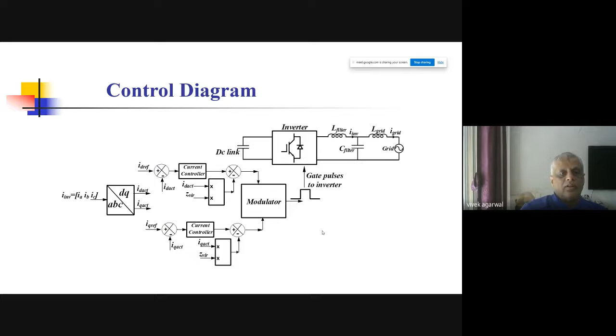Here is another example showing how you can use the sensed inverter output current to do protection. We've inserted an impedance such that at the time of starting the system, the large current coming out of the inverter and going into the system should be prevented. But we don't want this impedance to be there throughout.